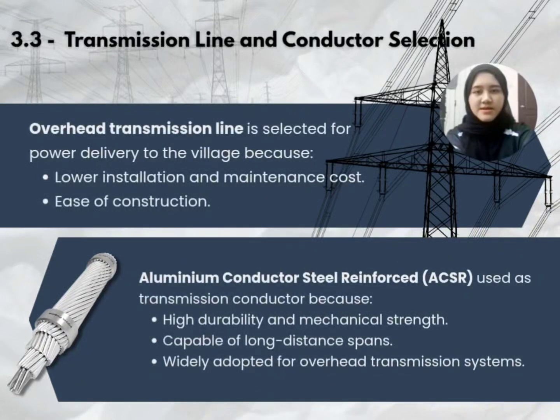Next, transmission line and conductor selection. For the physical delivery of the power, we opted for an overhead transmission line because this is the most cost-effective and practical solution for a rural environment. And for the choice of conductor, we are using aluminum conductor steel reinforced, or ACSR in short. This conductor is a hybrid. The aluminum layers provide excellent electrical conductivity, while the central steel core provides the high mechanical strength needed to span long distances with minimal sag.